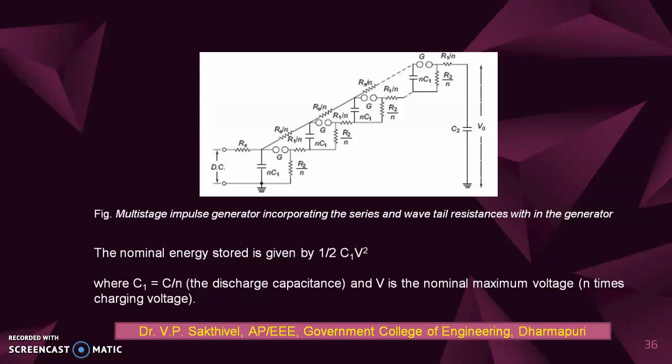Similarly, each resistor will be designed for a maximum voltage of 50 to 100 kV. The capacitor is an oil filled or compressed gas type with a capacitance of 1 to 10 nanofarad. Then the triggering system consists of spark gaps to cause spark breakdown of the gaps.